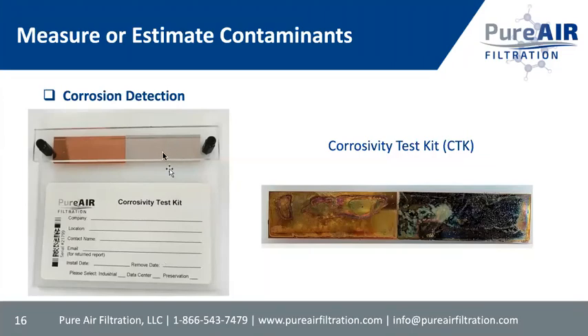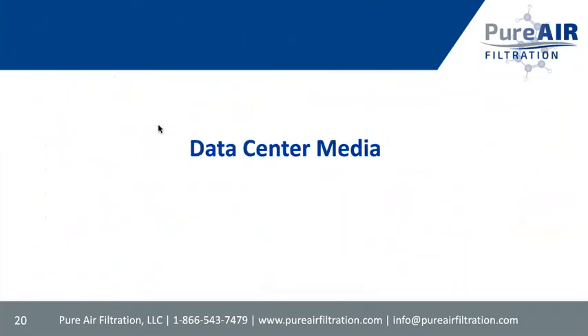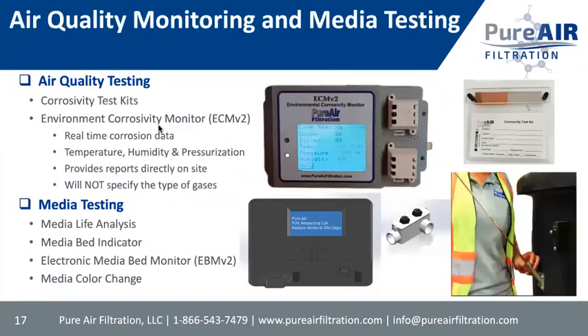The ISA standard, the International Society for Automation, says that to use one of these corrosivity test kits, we should deploy it in the room for 30 days. And after 30 days, the corrosivity test kit is sent back to our lab. We analyze it, and we determine how much corrosion is on the copper and on the silver strip. And according to that ISA standard, we report back as to whether that is G1, G2, G3, or GX. And I'll get to that in a second. So this is done every 30 days.